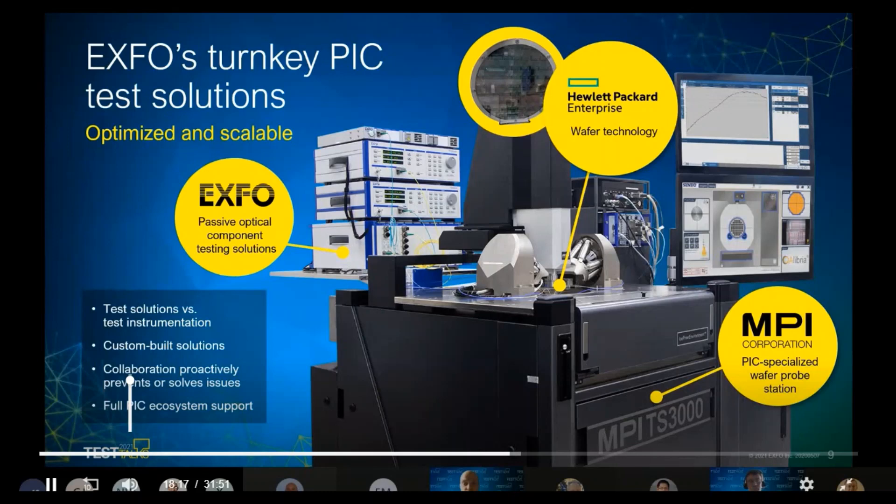It's a 300-millimeter semi-automatic system: we load the wafer manually and then automatically step through a wafer, align the fibers, and test the full wafer automatically. This setup is also available in a 200-millimeter version for smaller wafers, and also available with an additional loading option for a fully automated system where wafers can be loaded onto the chuck automatically. In the center we have two positioners — in this case, two hexapod positioners, which is the most advanced and most flexible solution, recommended for everything where we need to adjust angles, especially for testing fiber arrays where we need to overcome fiber array misalignment to the device.